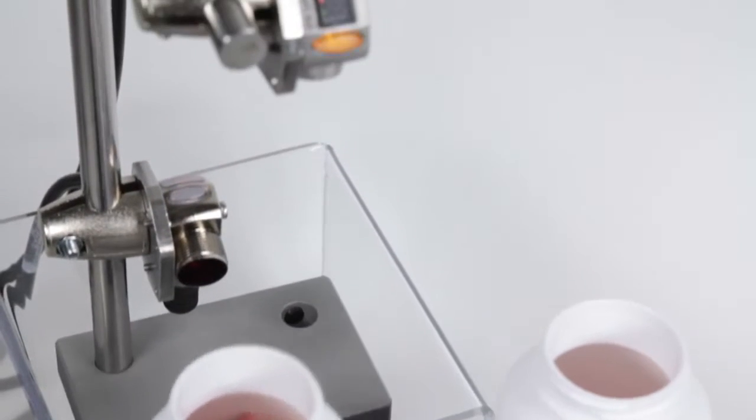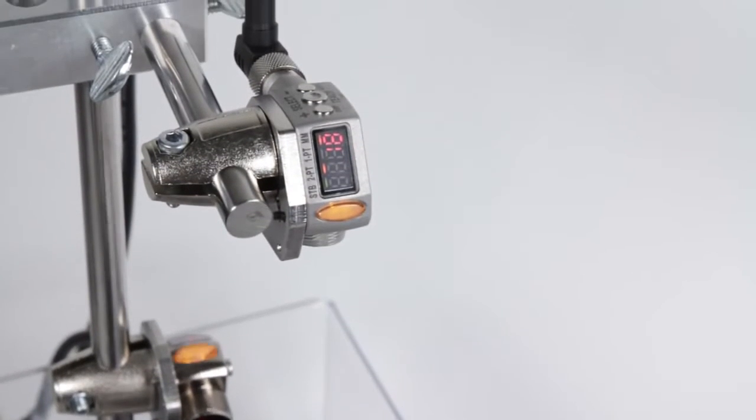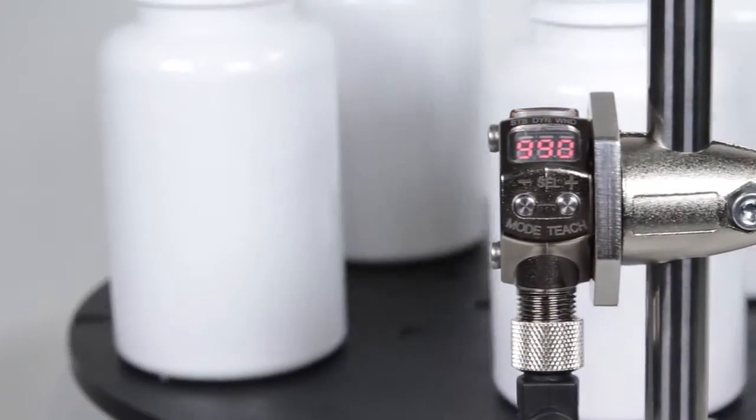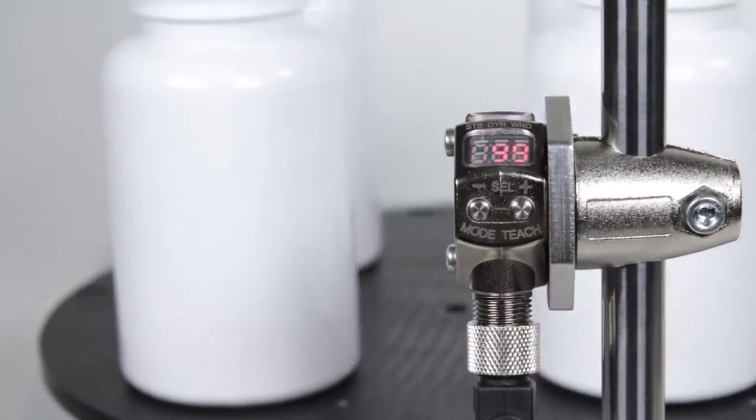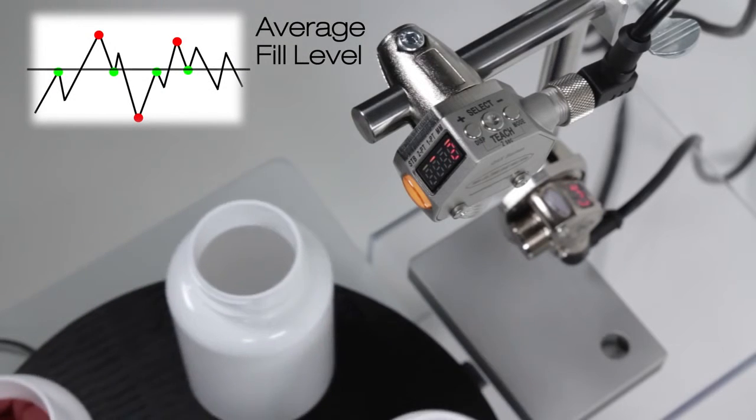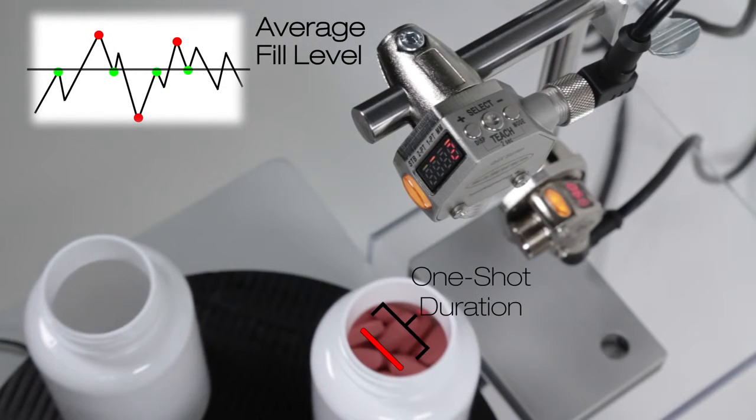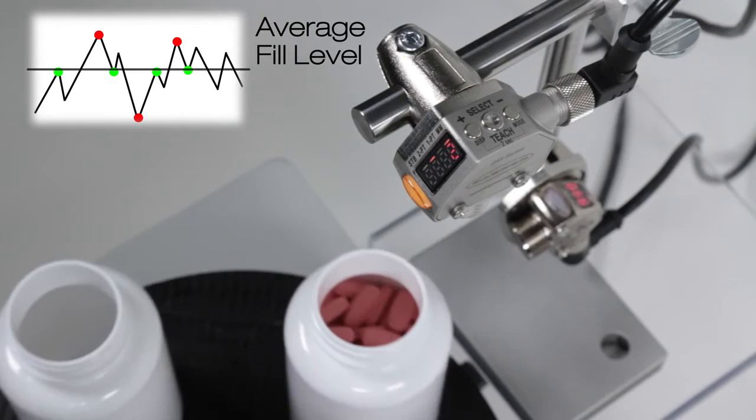The Q4X comes with advanced measurement modes, including a remote trigger input. In this case, a Q3X sensor is being used to send an extended one-shot discrete output to tell the Q4X when to measure and for how long. The Q4X will measure for a user-defined period of time and output a single analog output that reflects the average distance measured.